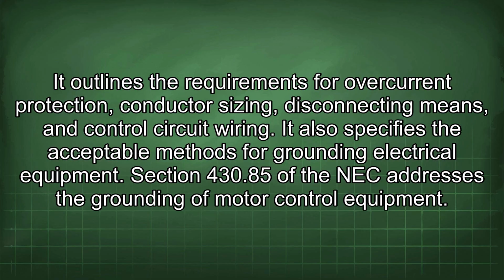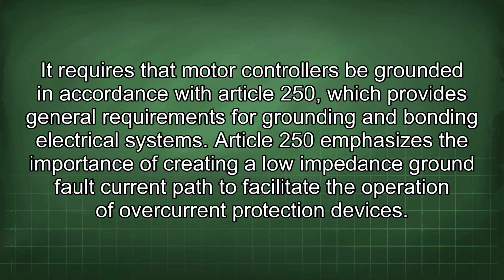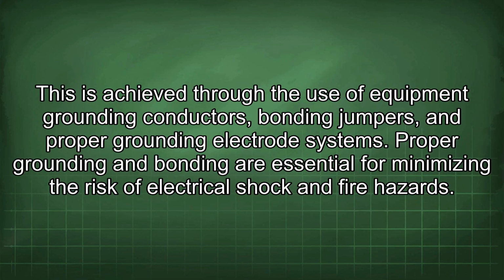Section 430.85 of the NEC addresses the grounding of motor control equipment. It requires that motor controllers be grounded in accordance with Article 250, which provides general requirements for grounding and bonding electrical systems. Article 250 emphasizes the importance of creating a low-impedance ground fault current path to facilitate the operation of overcurrent protection devices. This is achieved through the use of equipment grounding conductors, bonding jumpers, and proper grounding electrode systems.